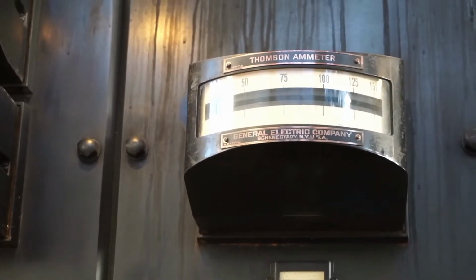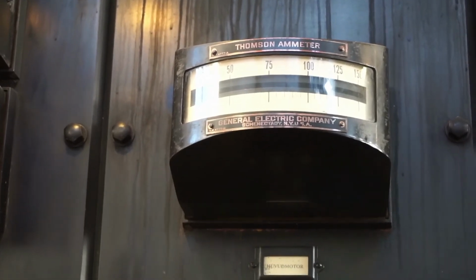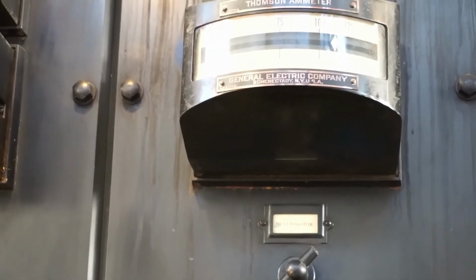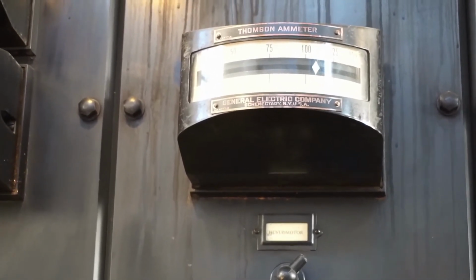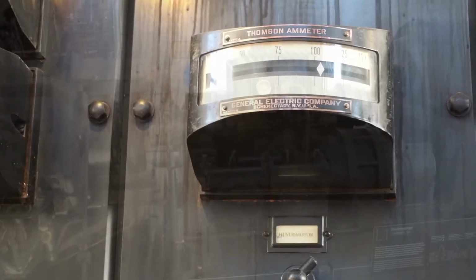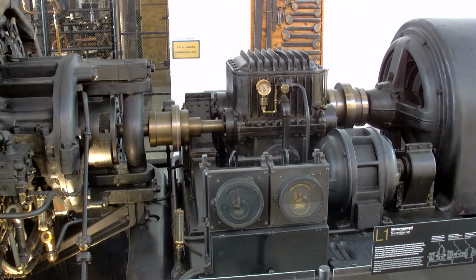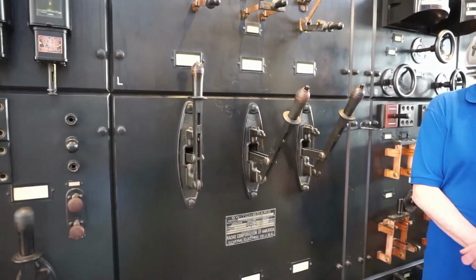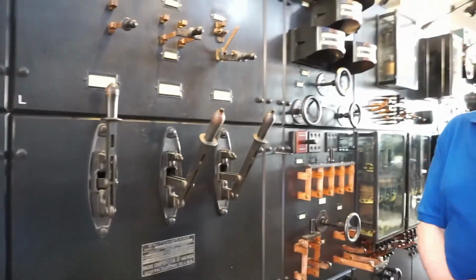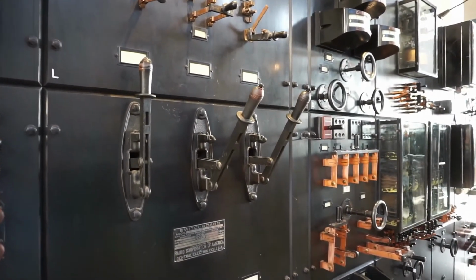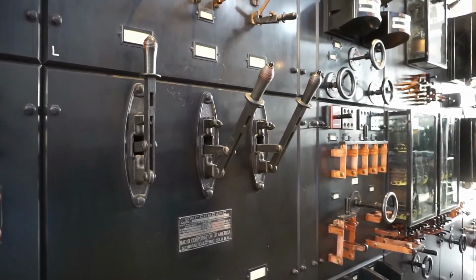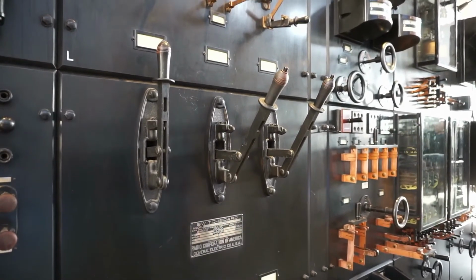The initial power to the main motor is limited by 4 choke coils in the power supply that will lower the initial voltage to 1,200 volt. And we are going close to 75 amps, and there Anders will start up 2 rectifiers. One will get 125 to 150 volt DC, and the other one is giving 500 volt DC. The 500 volt DC are used to saturate the transductor or the choke coils, so they will increase the voltage from 1200 to 2300 volts to get even more power on the motor.